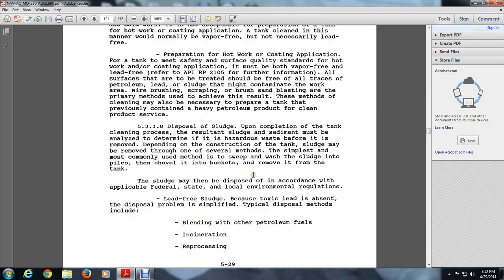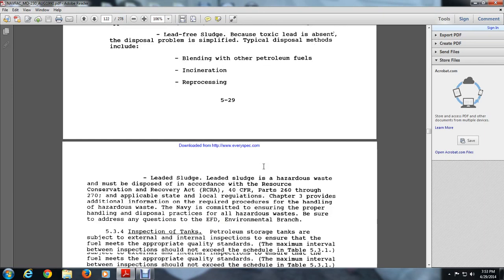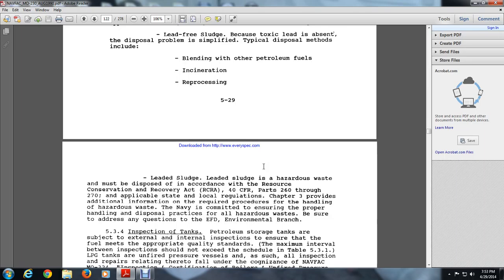5.3.3.8 Disposal of Sludge. Upon completion of the tank cleaning process, the resulting sludge and sediment must be analyzed to determine if it is hazardous waste before it is removed. Depending on the construction of the tank, sludge may be removed through several methods; the simplest is to sweep and shovel sludge into buckets and remove from the tank. Lead-free sludge disposal is simplified by typical disposal methods including blending with petroleum fuel, incineration, and reprocessing. Lead sludge is a hazardous waste and must be disposed of in accordance with the Resource Conservation and Recovery Act (RCRA), 40 CFR Parts 260 through 270, and applicable state and local regulations. Chapter 3 provides additional information on required procedures for handling hazardous waste.